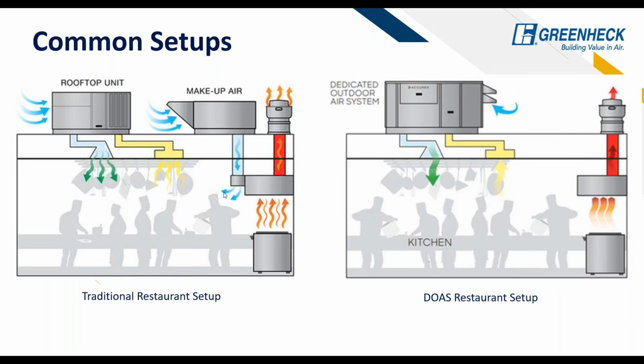And this is kind of what that looks like. Common setups would be a rooftop unit serving the air conditioning type stuff, and then a makeup air unit just serving the makeup air for the hood. Now you can combine the makeup air and the rooftop unit into a DOAS unit and serve both aspects at once, where you're tempering the space with air conditioning as well as providing makeup air for the hood. We're seeing a lot more of this nowadays.